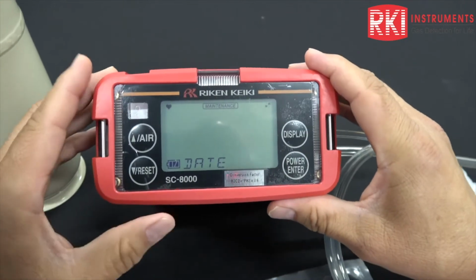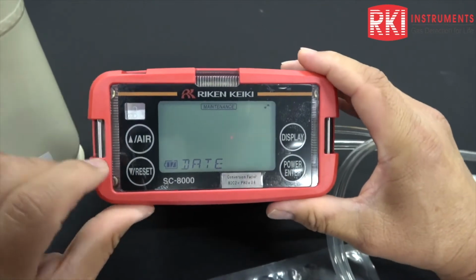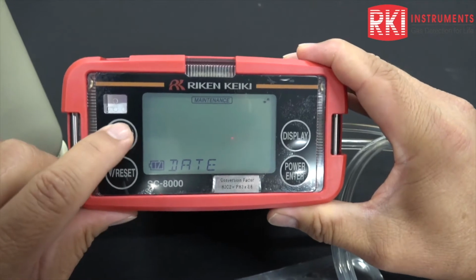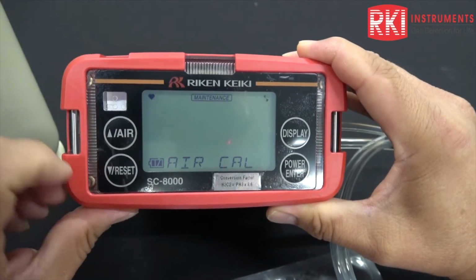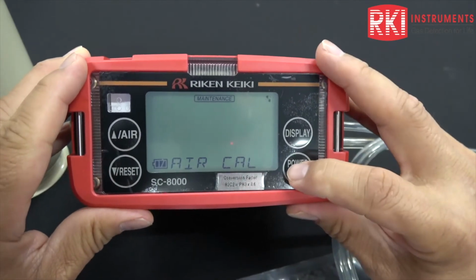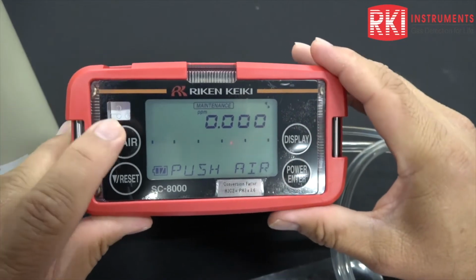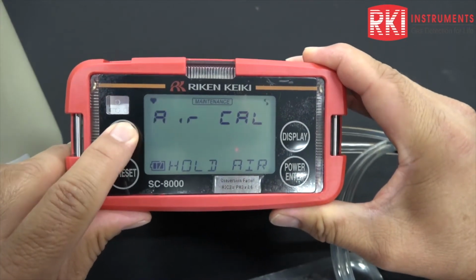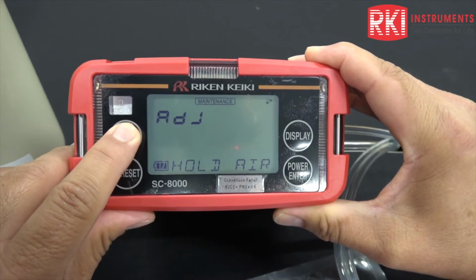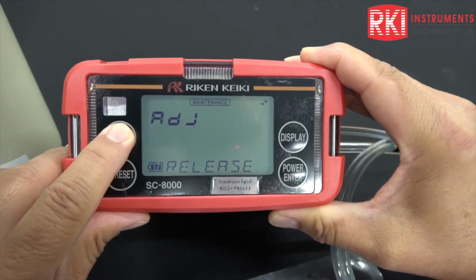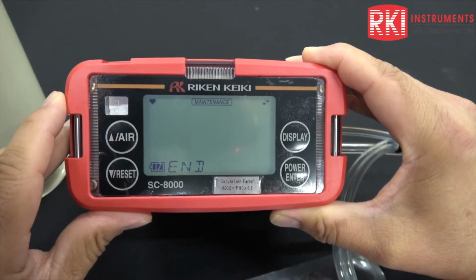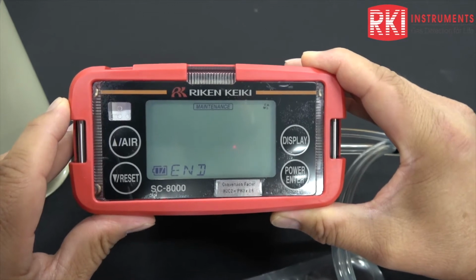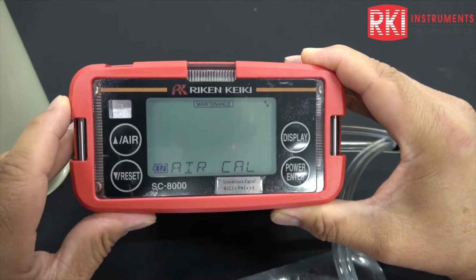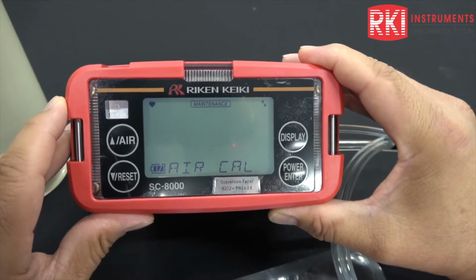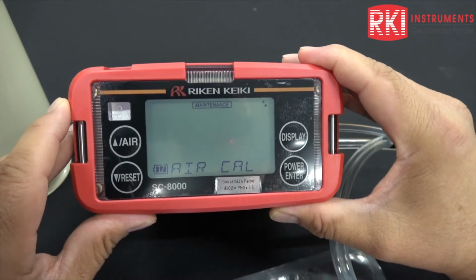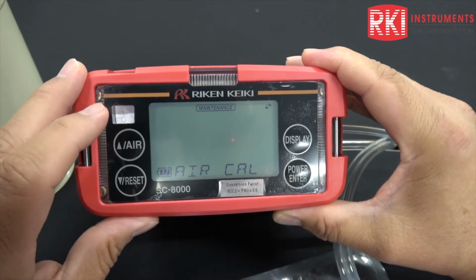Okay, so it brings up date first. So from date, we want to move to air. Okay, air cal, and then I'm going to press the power enter. And then I'm going to press and hold down the air button. And it says air cal, hold, air, adjusting, release. Okay. And now it says end. So it says completed the air calibration. That is successful. If it wasn't successful, we would get a fail right now. So we haven't gotten a fail indication. So we know that it was successful.